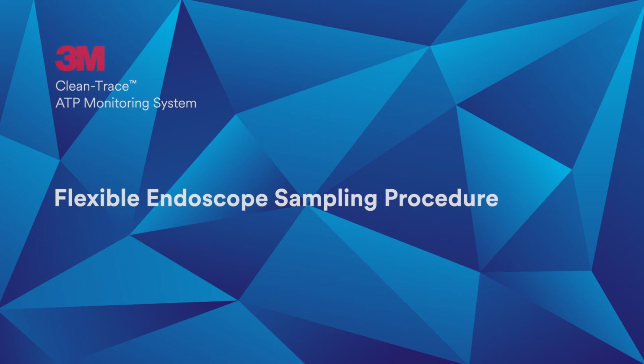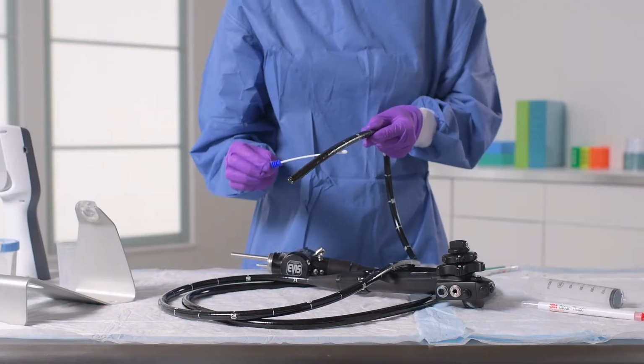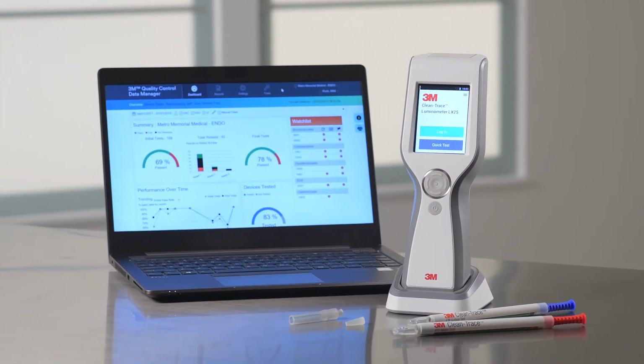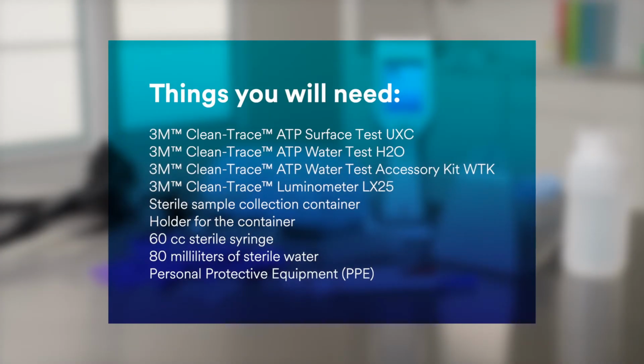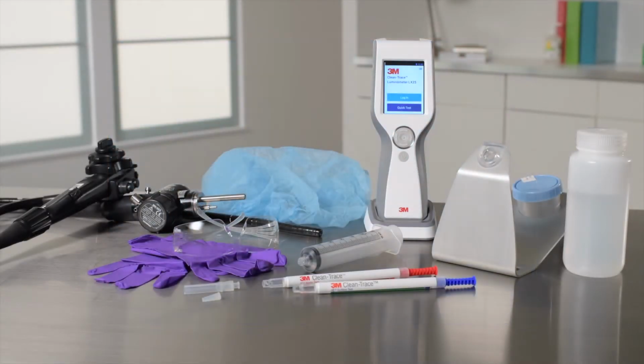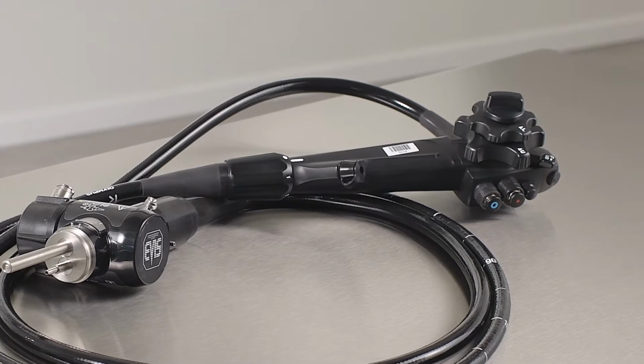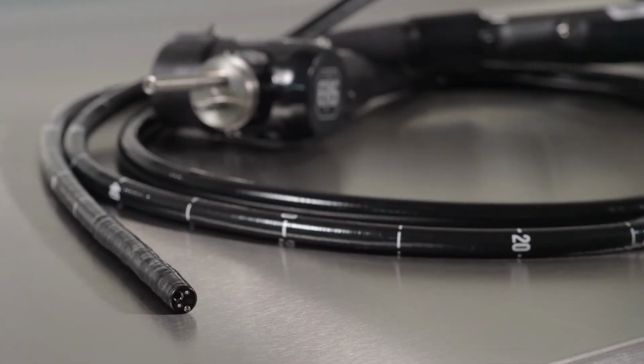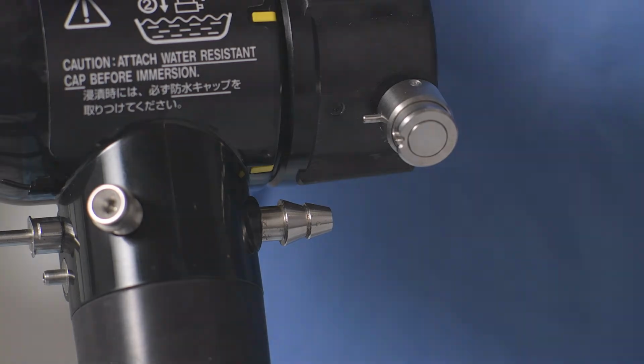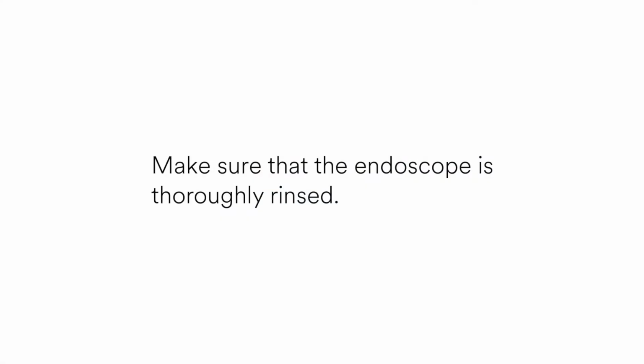In this video, you will learn how to collect a sample from a flexible endoscope to measure cleaning efficacy using the 3M CleanTrace ATP monitoring system. Endoscopes should be sampled after manual cleaning. On an endoscope, we recommend you test at least two test points, the outer distal end and the suction biopsy channel. Before you begin, make sure the endoscope is thoroughly rinsed.